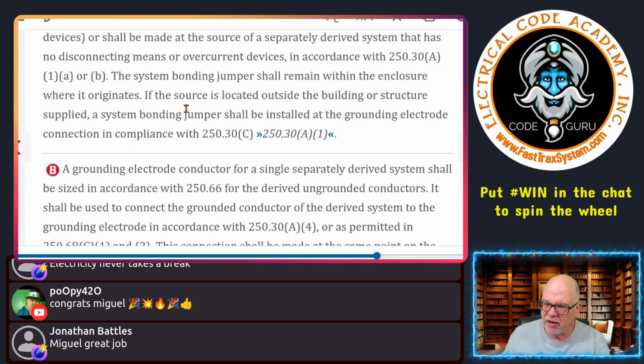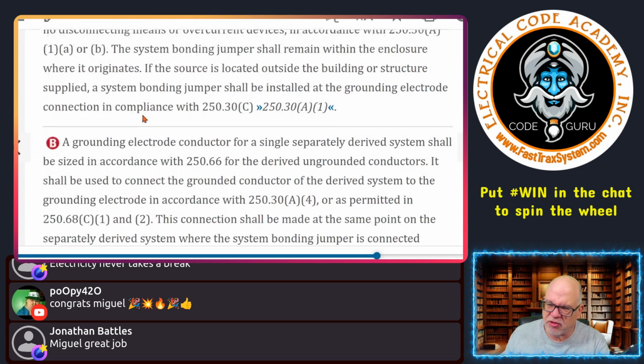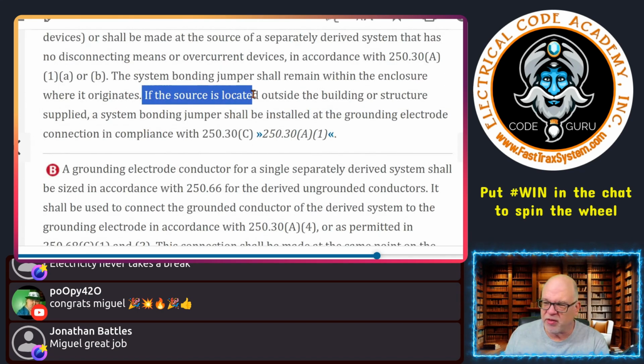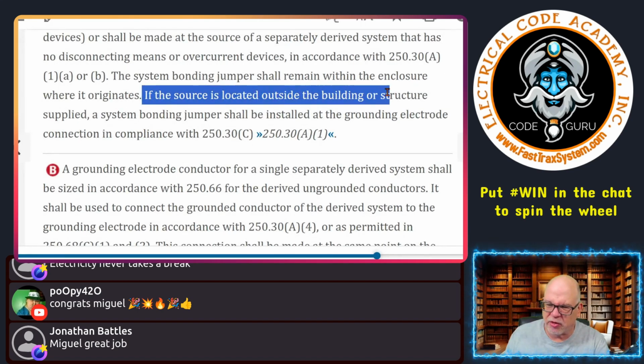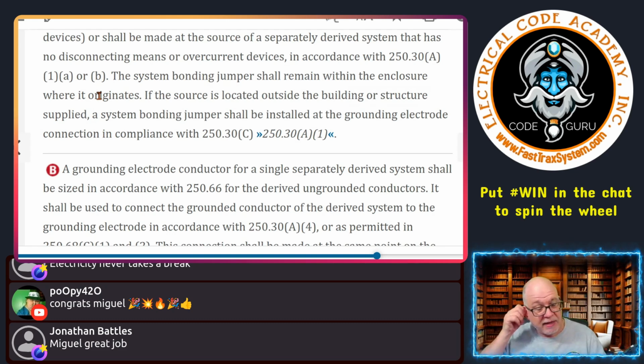Now, here is one that people ask about. What if the source, this transformer, is actually located outside of the building or the structure it supplies, okay? And we're not talking utility here, okay? We're talking about, let's say it's a premise transformer. It's stuck outside the building, and that's where the source is. And then it comes into a panel that's located, okay? Because these are like secondary conductors. Okay, they're not service conductors. If it's a premise transformer, it's not service.